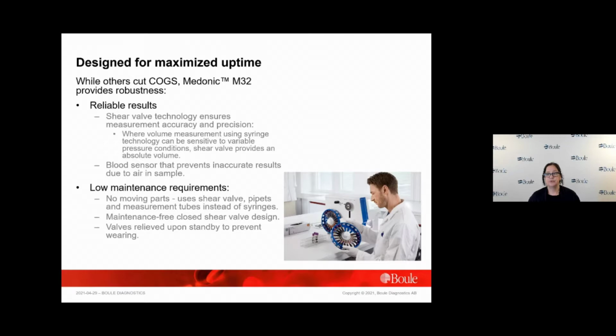Medonic M32 puts measurement reliability before cost. A syringe-based aspiration method is cheaper, but can be sensitive to variable pressure conditions. The more costly shear valve technology cuts an exact sample volume each time, independent of ambient pressure conditions. Additionally, the analyzer requires very little maintenance, which can be a costly feature, for example, for 5-part analyzers.